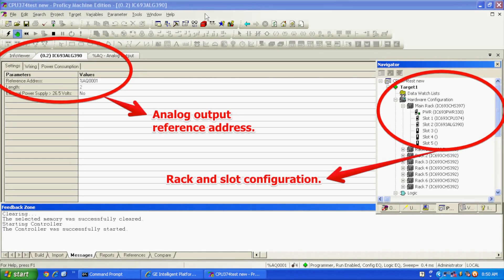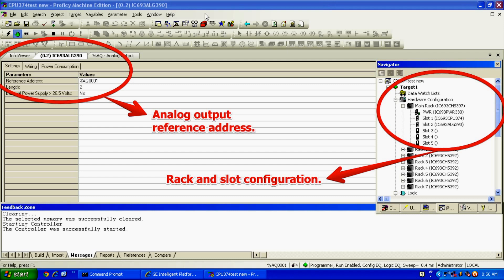If you open slot number two by double clicking on it, or you can right click on slot two and select configure. There's nothing really to configure on the ALG390. However, you do want to pay attention to where your reference address is, so that when you put a value into your analog output table, it's able to go to the proper destination and you're able to get a proper reading if the module's in good working condition.